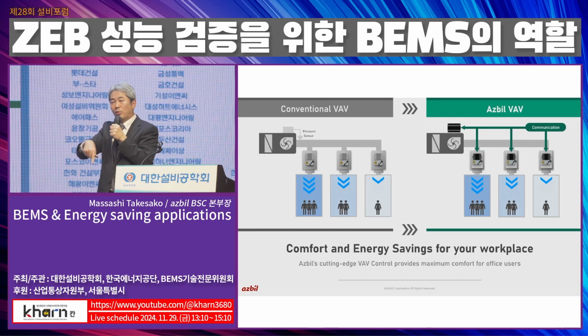So, according to the load fluctuation, we had better change the static pressure accordingly. That is the basic concept of the energy saving, the optimization. So with our control method, we don't need the pressure sensors. Instead, we try to get information from each VAV controller, and then maximize each VAV damper opening as much as possible.